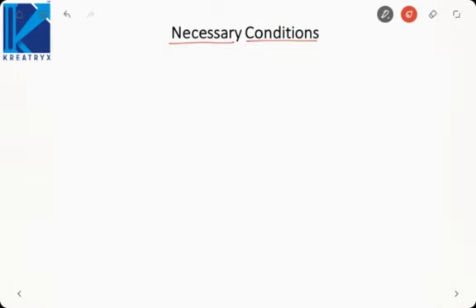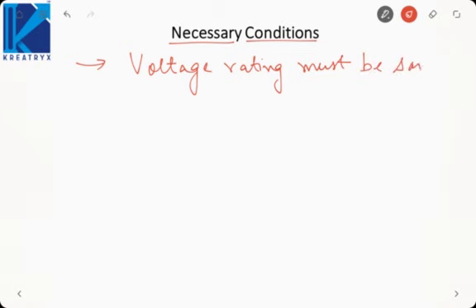Now, whenever two devices are connected in parallel, the voltage across them is same. So, similar is the case with transformer. When they are connected in parallel, voltage will be same. So, we will say voltage rating of transformer must be same. Okay, both transformers must have the same voltage rating. Next is both must be connected with same polarity.